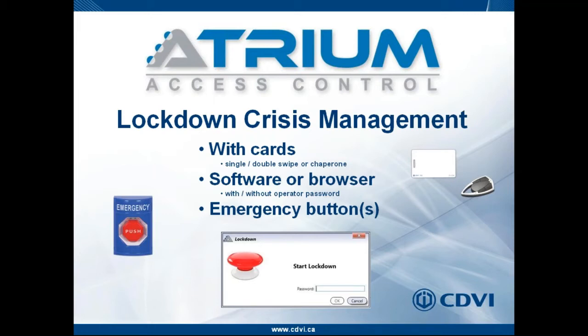The SWAT team will then evacuate the school class by class. So when I use my card as a SWAT team, I have the privilege to unlock the door even though we're in lockdown. It'll unlock for your unlock time in the system, which is by default 5 seconds. I will be able to enter the classroom, and if everything is clear and all is secure, I will be able to evacuate the children from the classroom and outside the building. When I'm done, I will be able to use a second card to indicate to the system that the area has been secured.